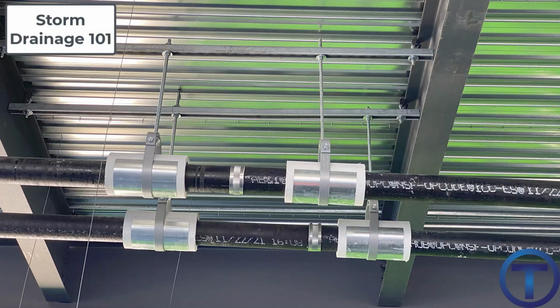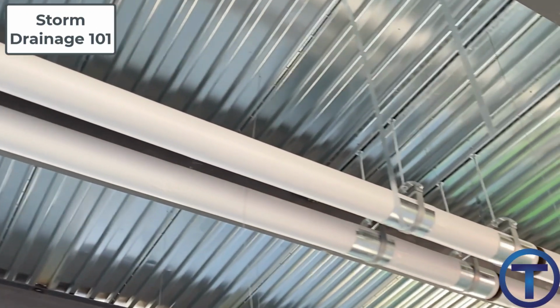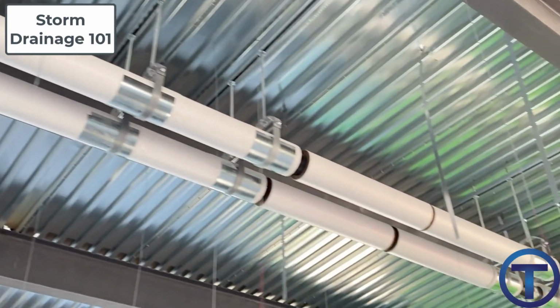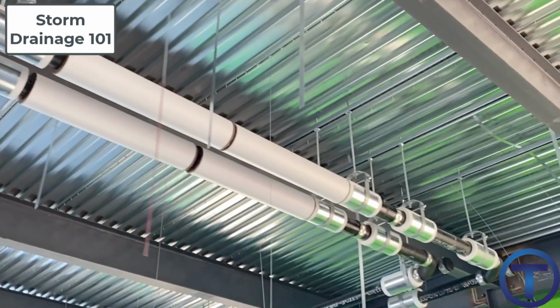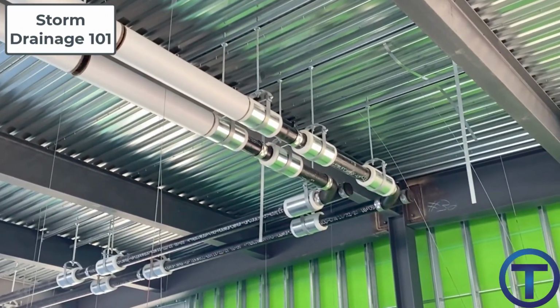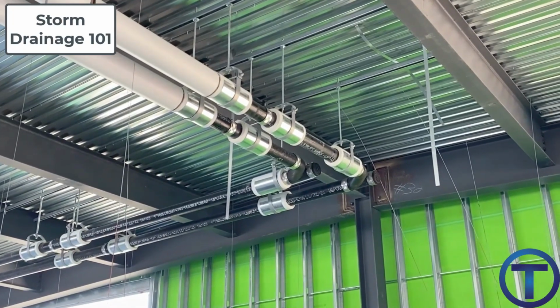The insulation that is installed in those hangers is a rigid insulation made of calcium. They're calcium blocks that can hold the form but also insulate the pipe. So when creating roof drain Clevis hangers, make sure to leave enough all thread so that those Clevis hangers can be adjusted down as that insulation is added.